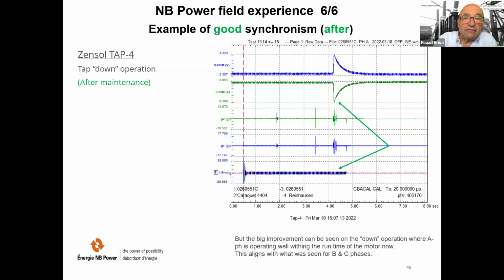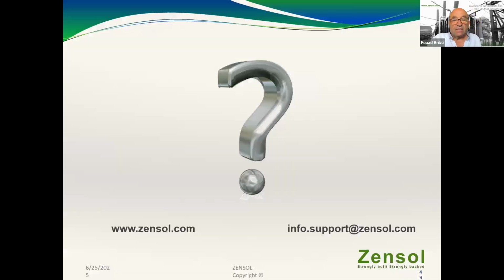And here, after maintenance, the big improvement can be seen on the down operation, where A phase is operating well within the runtime of the motor now, and this is aligned with what was seen for B and C. So now you see that the diverter occurs on phase A before the end of the current. So this was solved.